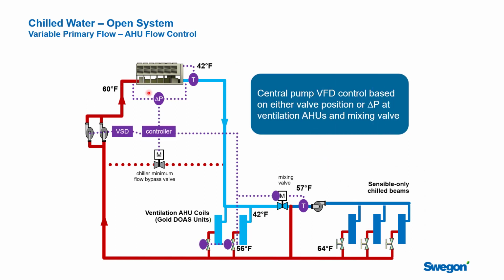Up here, let's talk a little bit about what's going on in the main loop that's servicing the air handling units. So again, you could put a pressure transducer near the air handling units and maintain the pressure for this loop. Again, as the air handling units require more chilled water, their two-way valves will open. They'll require more flow. That'll drop the pressure, because that'll send a signal to the primary pumps to speed up and increase the flow out to the air handling units. The reverse would be true if the load starts to drop off in the air handling units. These valves will close, the pressure builds up, and that causes the pumps to slow down.